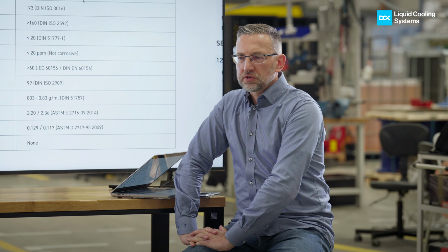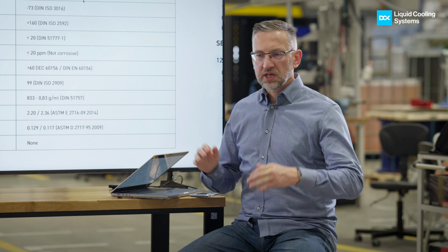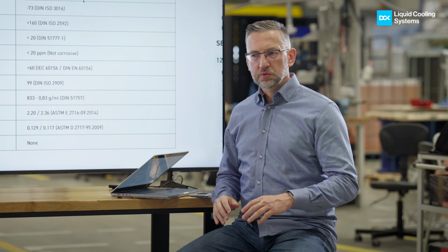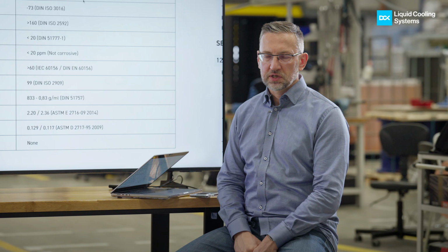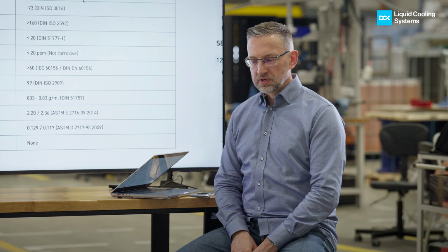and that breakdown voltage is important because it degrades over time. When you start getting a slightly higher water content, because it picks up some humidity from the air, then the breakdown strength is lower. So I guess 50 to 60 would be reasonable to expect from the coolant. And obviously specific heat between 2.2 and 2.3 is something we can expect. Thermal conductivity, no solubility in water, so basically it must not be hygroscopic.